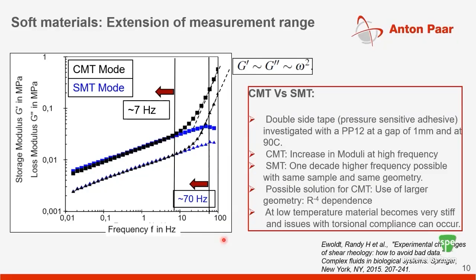There are different solutions one could do to increase this range if you just are stuck with the CMT mode. One can actually use larger geometries, and maybe it will become more clear in the next slide where I show you some equations, how you can extend the range if you just have a CMT mode by using a larger geometry. But typically larger geometries don't really work in the PSA industry because typically, people are doing temperature sweeps and stuff in this industry where the material really becomes very stiff at the low temperatures, and you kind of need to worry about torsional compliances. And typically you go with smaller geometries.